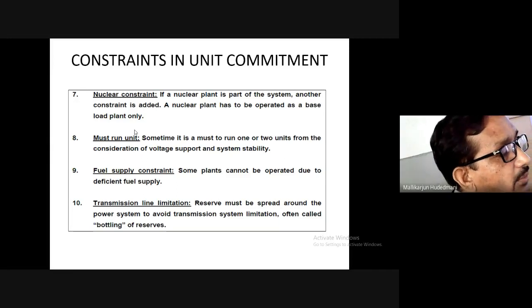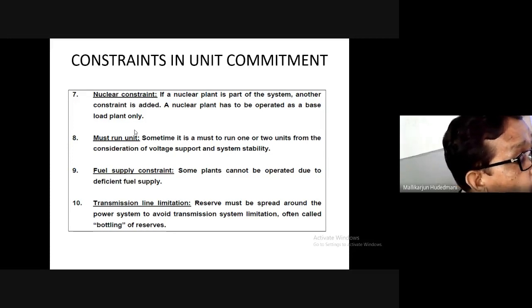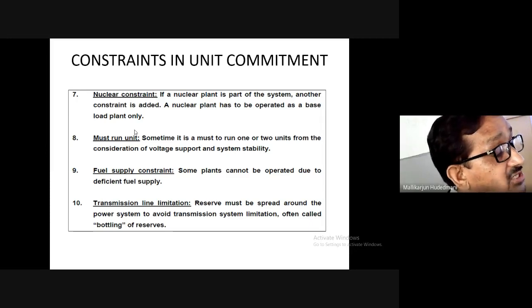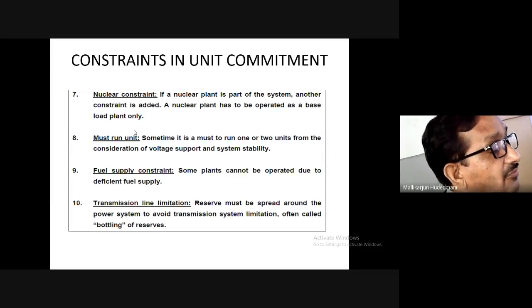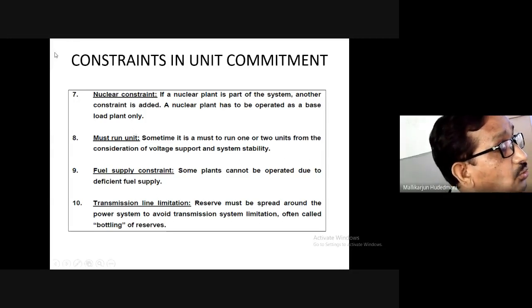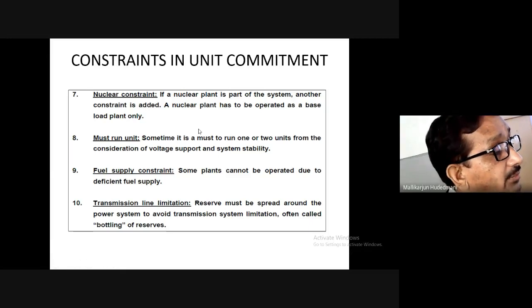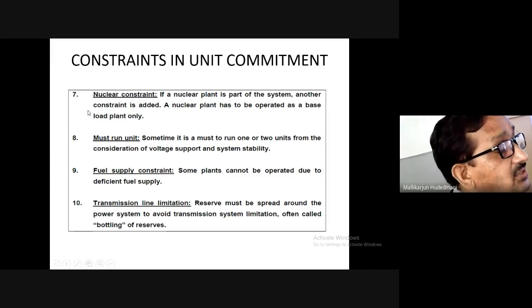What do you mean by top-up? When I have a load curve on the station and divide that load into three sections, the lowest load is addressed by base load generators, the central part of the load curve is addressed by intermediate load generators, and the topmost crest part is served by peaking generators. In these three bands of generation categorization, nuclear plants and hydro plants serve as base load because they are set to generate constant megawatt output with respect to permitted availability or granted permissions.